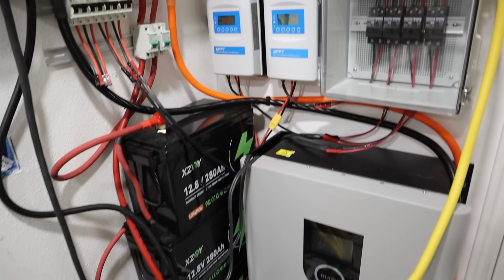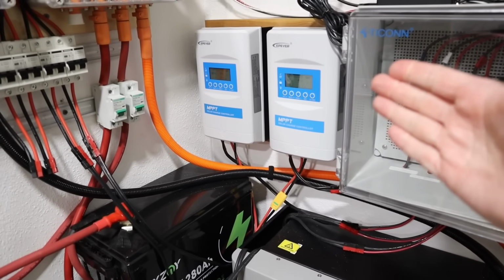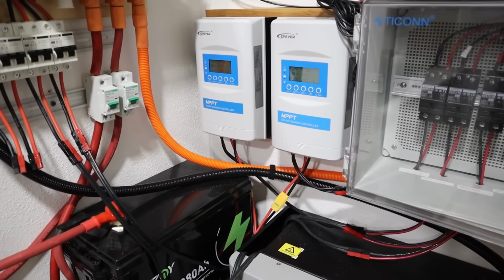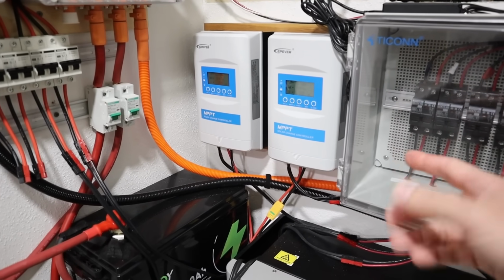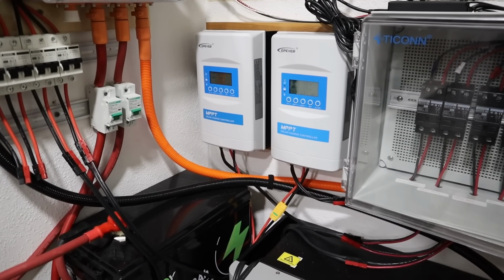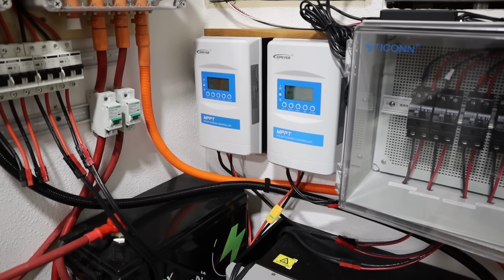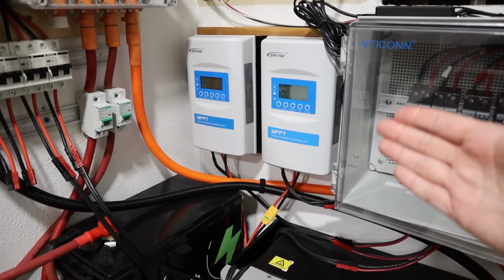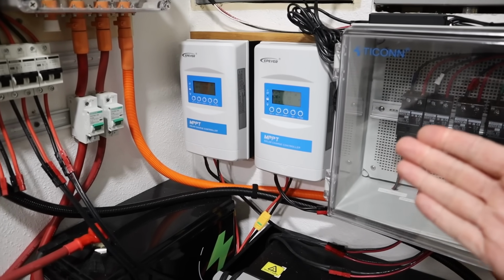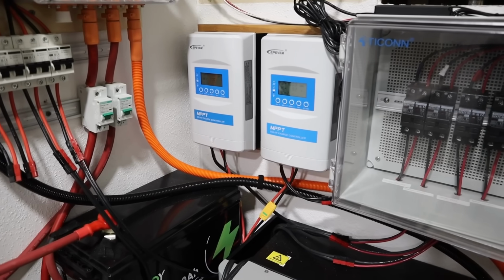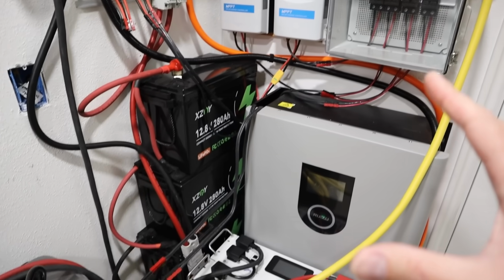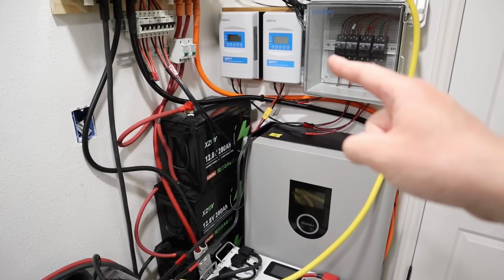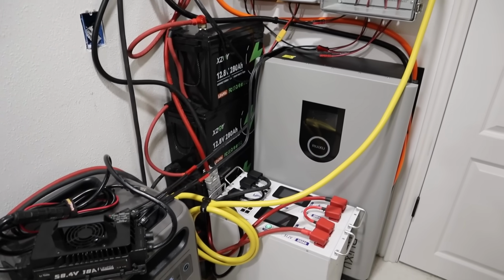Now, luckily, my charge controllers over here have an adjustable setting for the voltage. These were originally set to lithium iron phosphate 48 volts, but what I've done is I've actually set them both to lead acid gel batteries, which has a slightly lower voltage, and it's actually been working really well. These batteries still get up to full charge using the charge controllers, but they don't quite hit 58 volts.